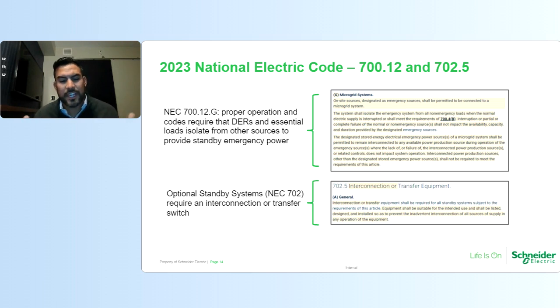So essentially, when you're designing these systems and you intend to use the energy storage system for emergency power, you want to make sure you have your emergency loads separated on different panel boards or switchboards, where in the event of an outage, you can safely disconnect from the utility and segment those specific loads for emergency power, as indicated in the National Electric Code. And then as well, the code references that interconnection or transfer switch equipment is required as a means of interconnection and transfer. So it shows you here that an interconnection switch is an acceptable means of connecting to an emergency power source for these applications.